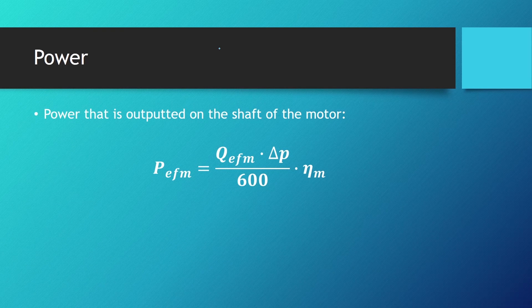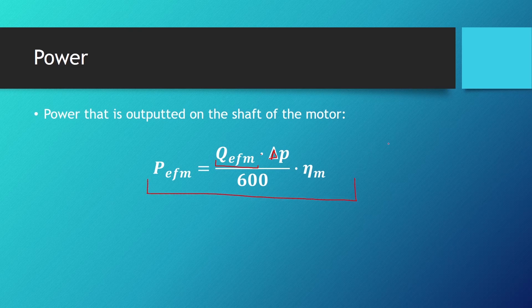Now, power. The power outputted on the shaft of the motor is calculated by taking the effective flow of the motor times the achieved pressure difference, divided by 600 times the efficiency of the motor. When you put flow in liters per minute and the achieved pressure difference in bars, what you get from this equation is kilowatts.